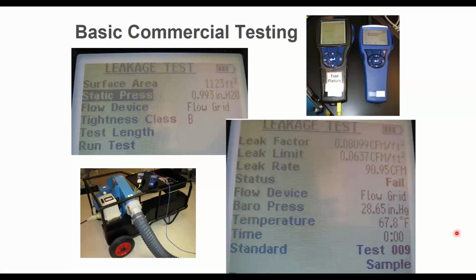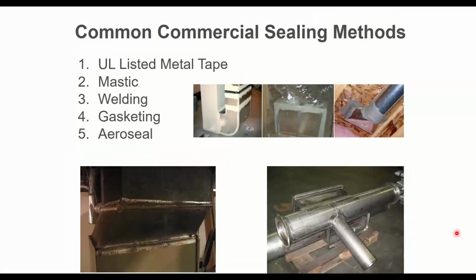Okay, so, and then you're going to get some kind of report. Looks something like this-ish. Depending on what kind of manometer and machine you're using, that tells you how much leakage you have at what pressure testing. All right, so then you decide to make some improvements. You're going to seal the duct, either because it's a new job and you have to do it by code, or because it's an existing job and you just want to make improvements to save energy, improve air quality. I didn't even mention that.